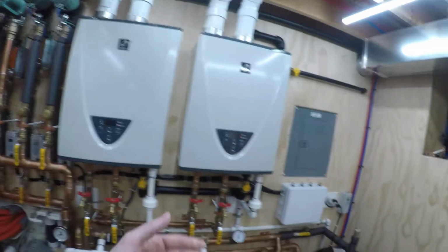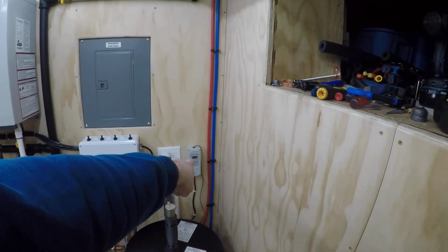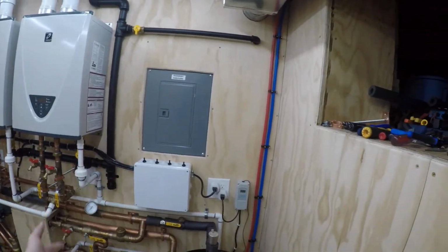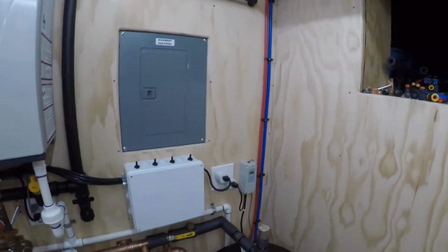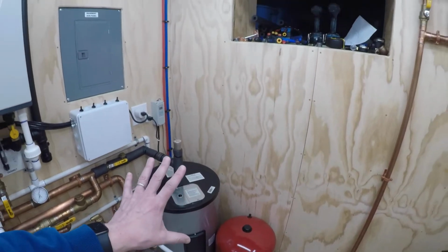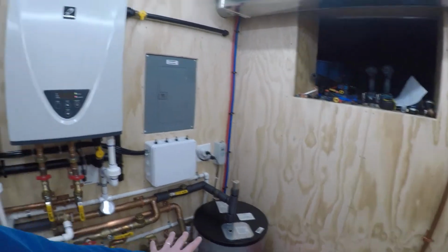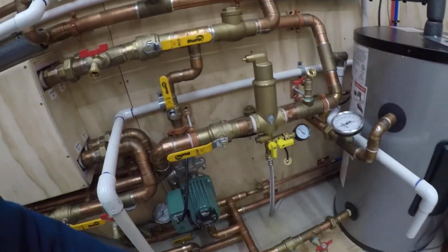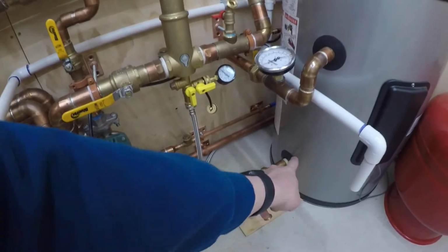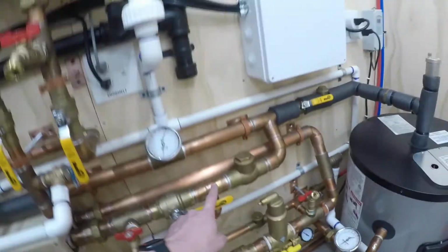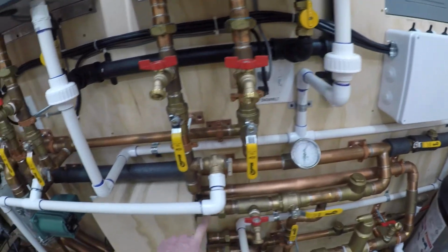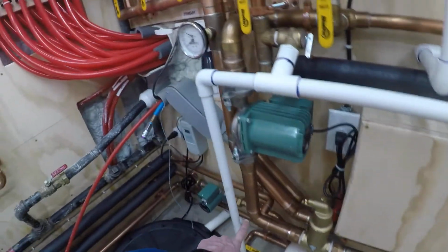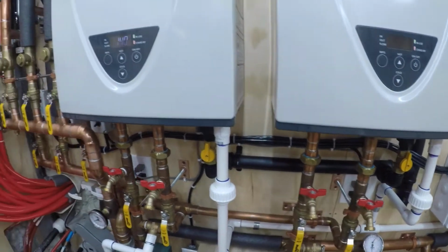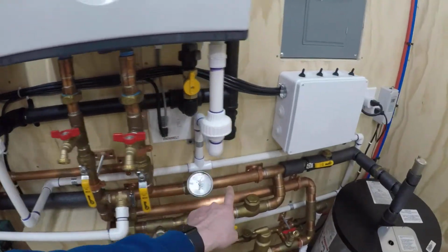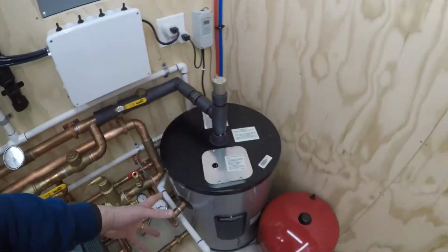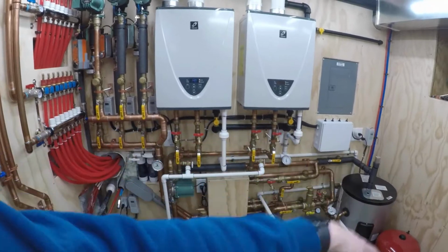But it doesn't turn on the tankless units unless this drops. Now that's at 126, and at 125, it's going to fire the units. So you'll actually get to, okay, just hit 125. So what just happened there is the sensor inside that tank says, hey, the tank's getting a little cold. I need some hot water here. Okay, it turns on this pump, and the pump starts sucking water from the bottom of the hot water tank through this zone, over, through the pump, and into the primary loop. So right now the hot water is going through the flat plate heat exchanger, which I'll explain in a minute, around, up, into the tankless units, okay, out of the tankless units, over to here, and back in the top of the tank. And right now, since there's no call for hot water, that's just circulating, okay?